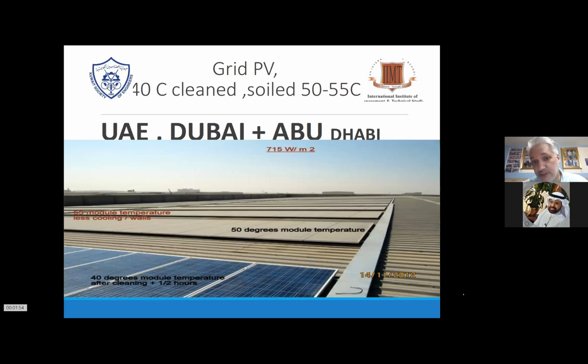So some inverters, especially during 2010, 2015, had quite a narrow MPPT window. And if you did not give him enough MPPT range, you must imagine in summertime, those modules per panel are losing roughly between 3 and 5 volt. So depending on the angle and the heat and the influx of energy, one module loses at worst 5 volt. That means a string of 18 or let's say 20 modules loses already 100 volt. So these 100 volts you will never get back to the inverter. Hence, they will suffer the consequences during hot periods of time. So in winter time, you win a little bit, like 0.5 to 1 volt maybe, and also the current goes up.